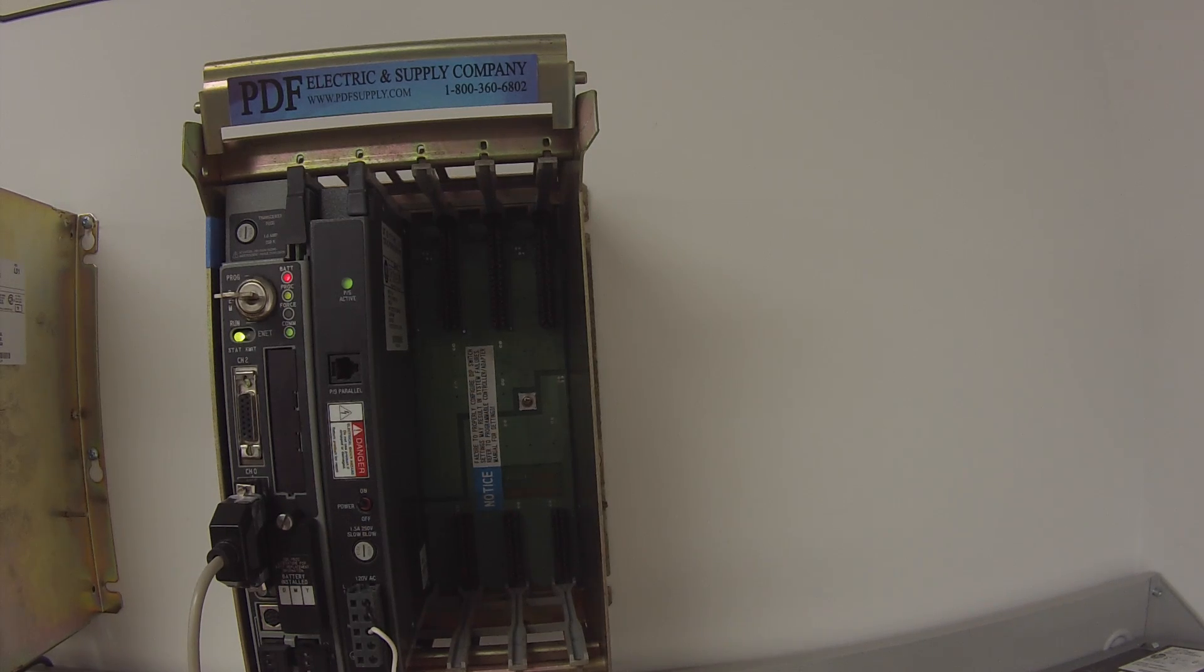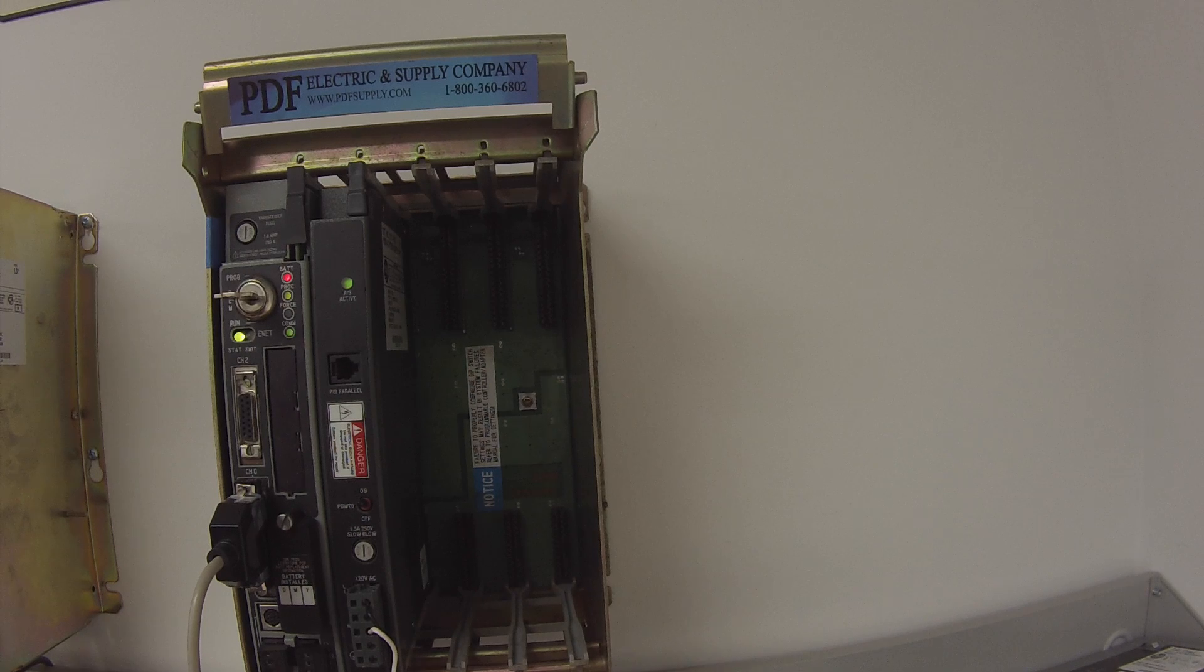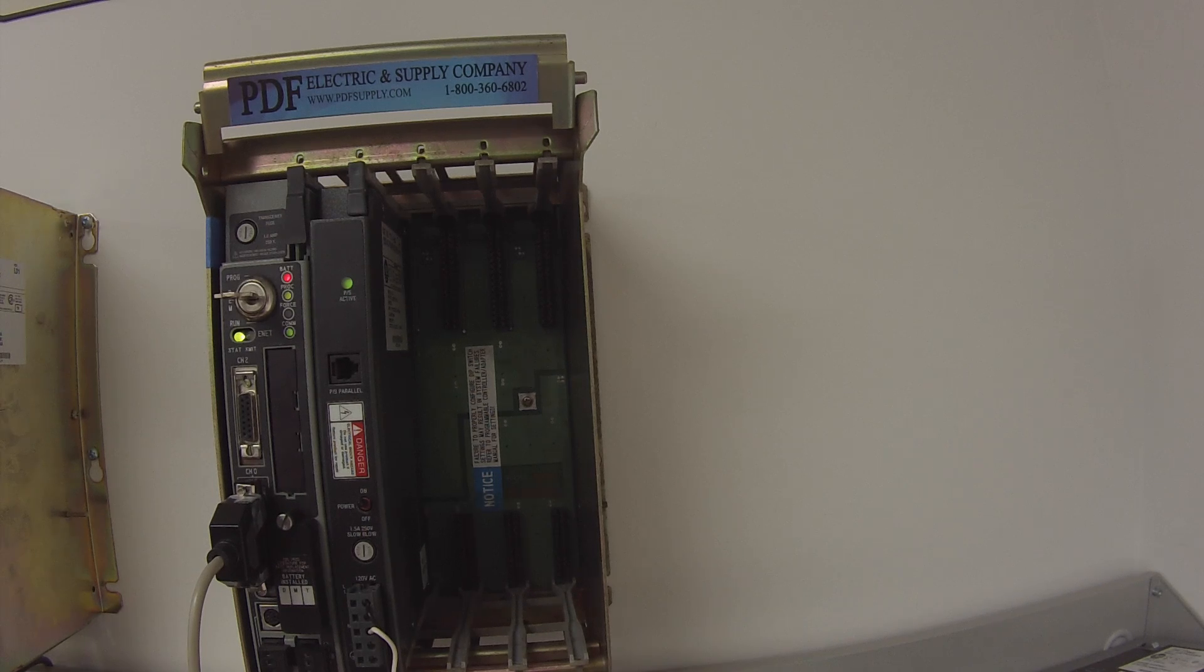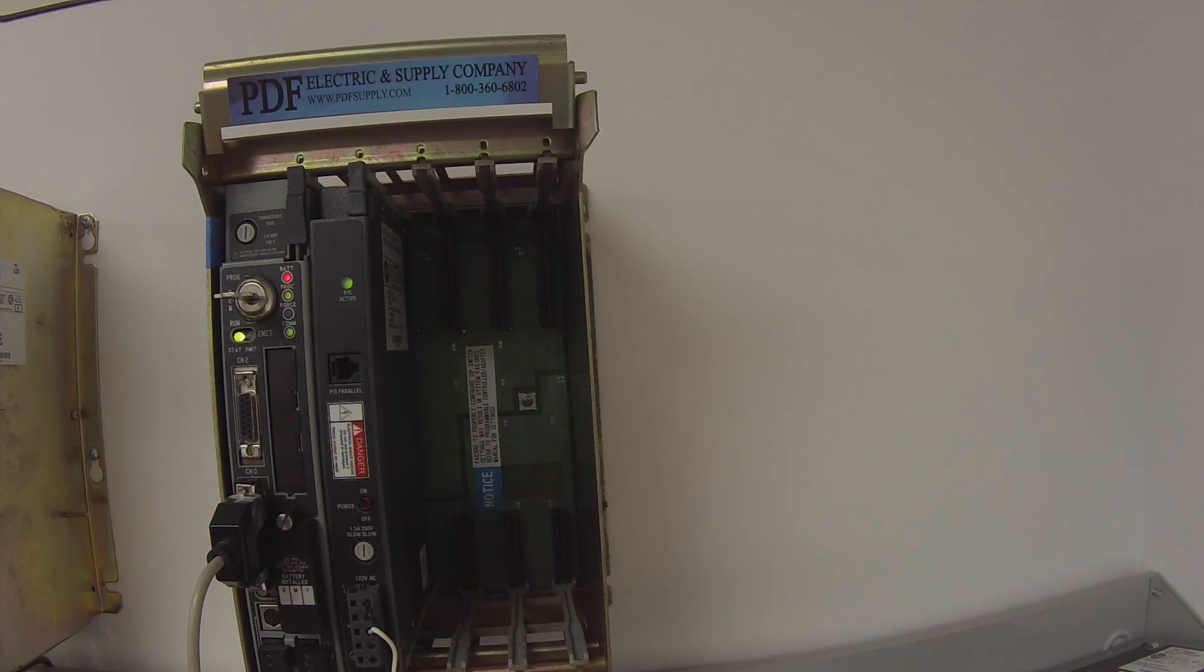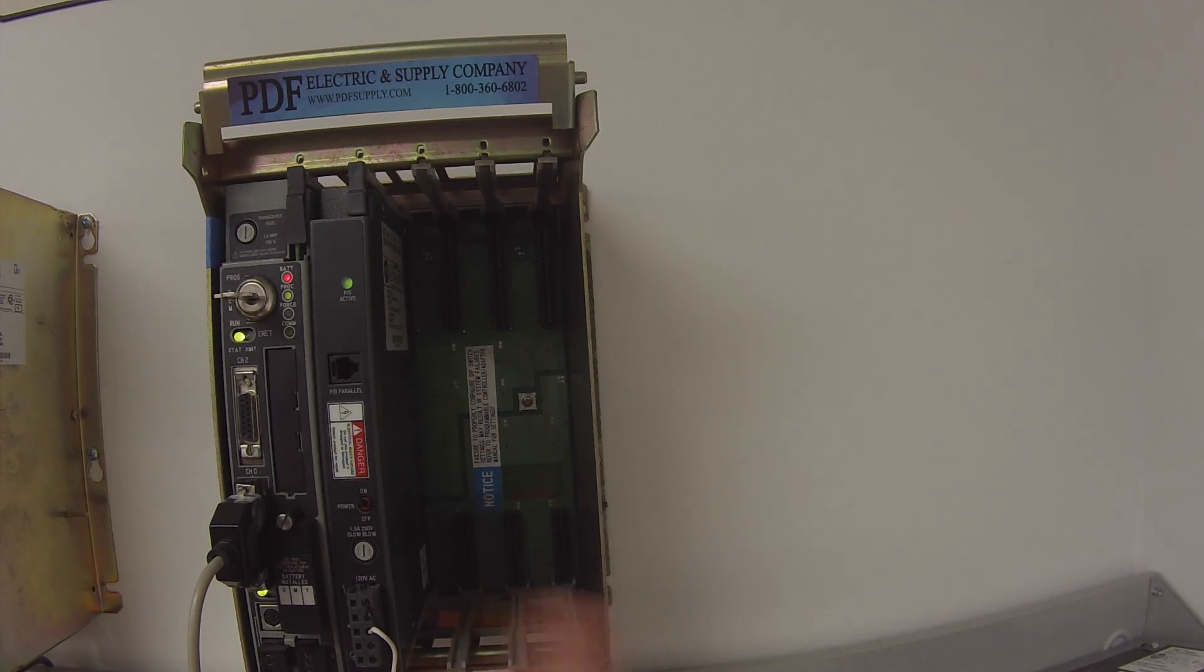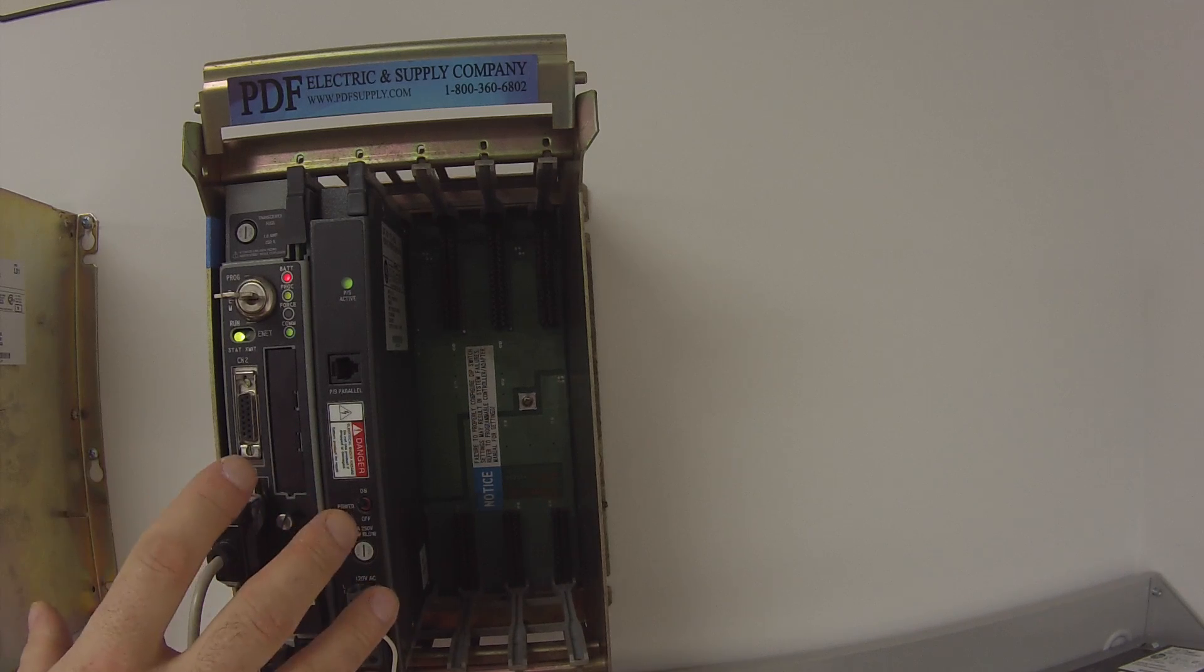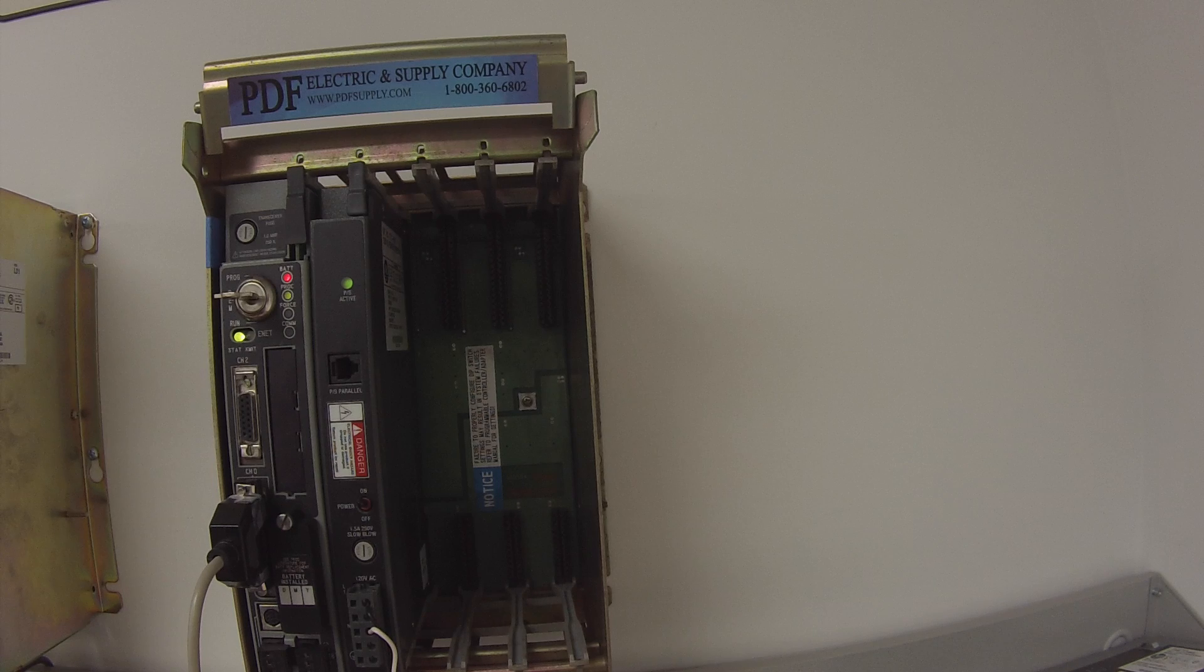The next thing I'm going to do, two other things here quickly. Go to processor status and double click on that. In the menu there, the tab that says errors. I'm going to go to that because if some sort of an error occurred when you guys were using it or if there was some sort of a problem, it'll usually leave an error code or a fault code that tells you what the problem is. If it's something that is very minor, maybe you switched out a card to a newer revision and it set off an error or a fault, and you know that's just a very minor thing and you're aware of it, you could go ahead and hit clear major errors.